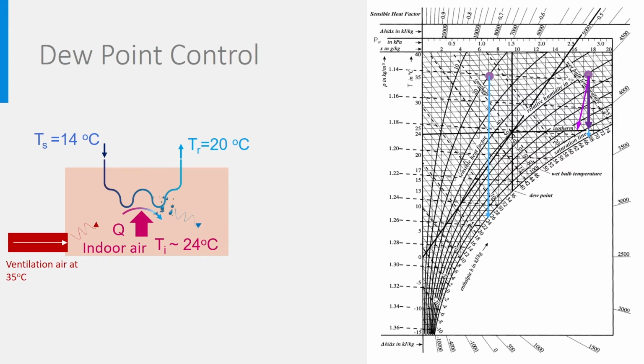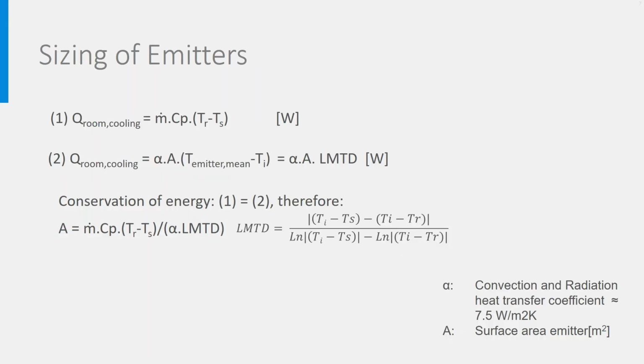Just like for the heating mode, we can size the emitter by using the law of conservation of energy and the log mean temperature difference. You may remember that in heating mode, the temperature difference between supply and return was around 20 degrees. In cooling mode, it is more limited because of dew point issues. In the example on the previous slide, the temperature difference was only 6 degrees.